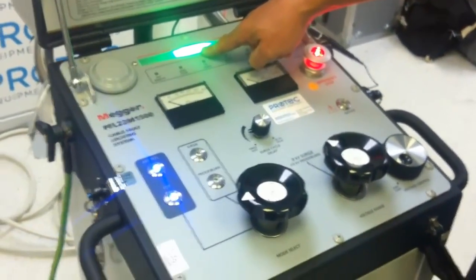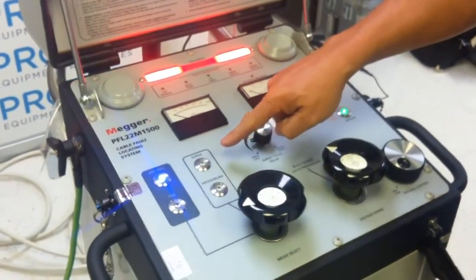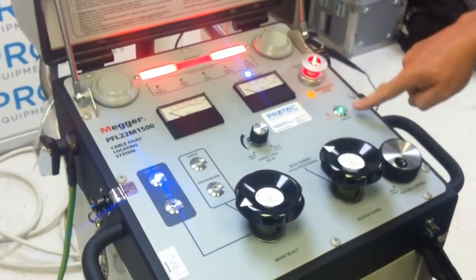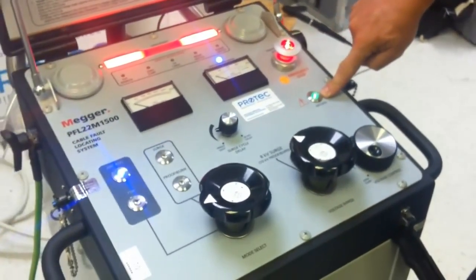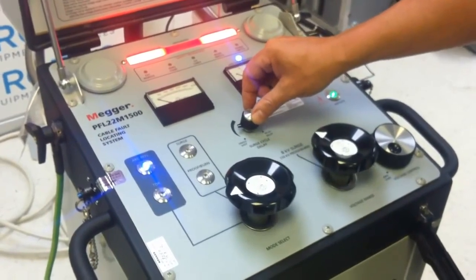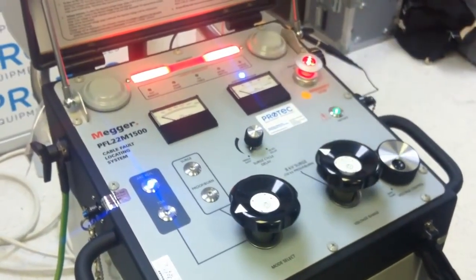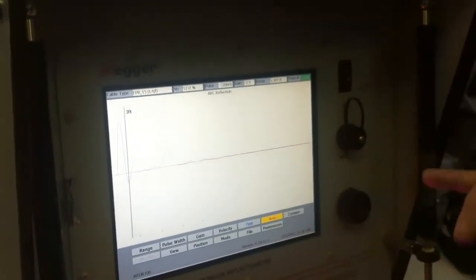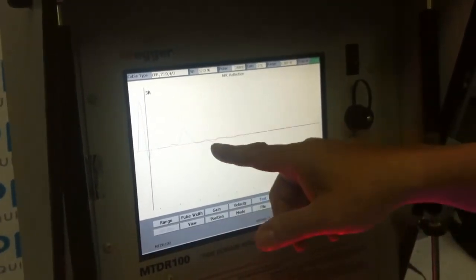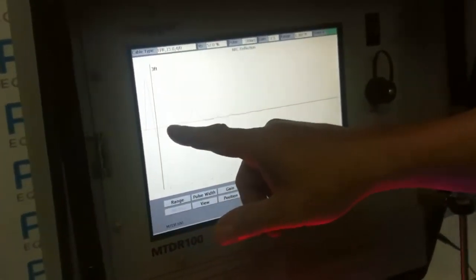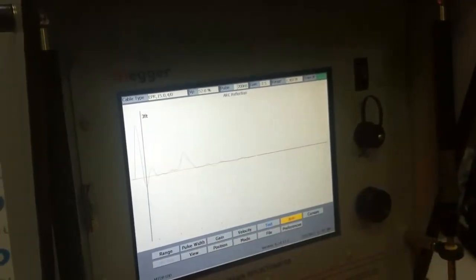To run the arc reflection test, I simply select arc reflection. Again, I go to an elevated test mode, but notice now my initiate lamp comes on, allowing me access to the high voltage system. Now, for an arc reflection test, I do like to work in a single shot. We will go ahead and cancel the low voltage TDR test by simply pressing down on the knob. I will now go to my arm, and the way arc reflection works is we actually take two pictures of the cable. The first picture is with just the low voltage high frequency energy of the TDR radar capturing events along the cable path. I can see the end of the cable, I can see my connection to the cable, I can see my instrumentation or my energy leaving my radar.